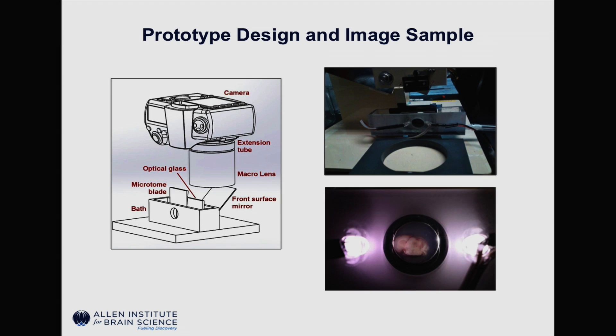Taking those requirements, the engineering team came up with this design. This is based upon an initial block-based imaging system used during the Human Brain Atlas Project and the Non-Human Primate Atlas. It had a Canon camera, used a custom-designed buffer chamber, and acquired images in color. The images were integrated into LIMS, which proved we could use them and the parts were all readily available so we could make multiple units. There were a few problems though: the smaller buffer chamber made it difficult to carefully pick up the slices, and the images were a little bit small for actual registration use.